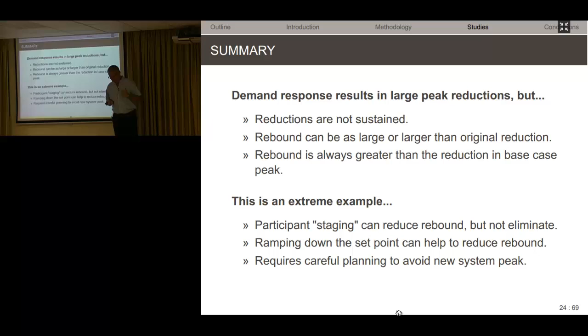So let's see where we are. Demand response has large peak reductions, but the reductions are not sustained—it's a matter of time until we get back. The rebound can be as large or larger than the original reduction, as we've seen, and we can improve the situation. This was an extreme example. We can use staging, as I mentioned, ramping the set point down instead of taking it immediately from 2 Kelvin above your set point down to your set point. You can stage it down, and that might help, but it's not good—so this will serve as our benchmark.